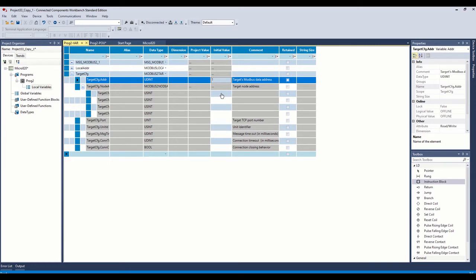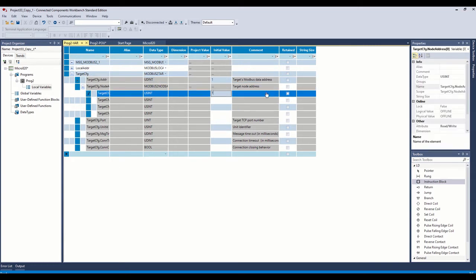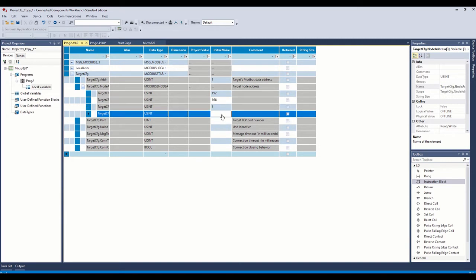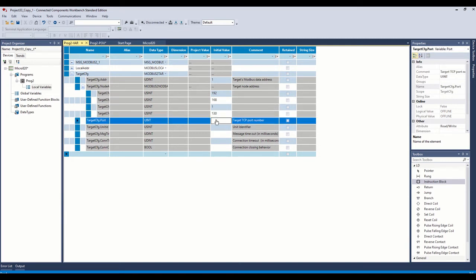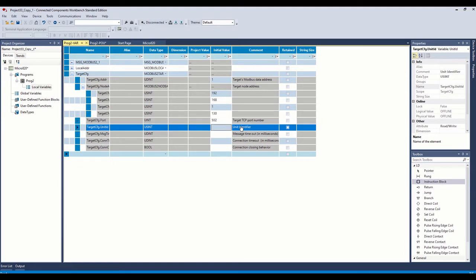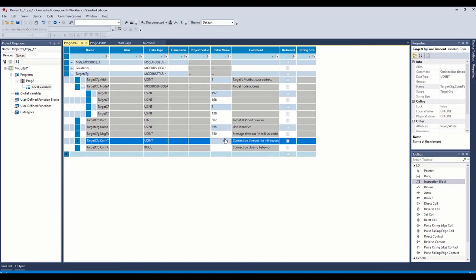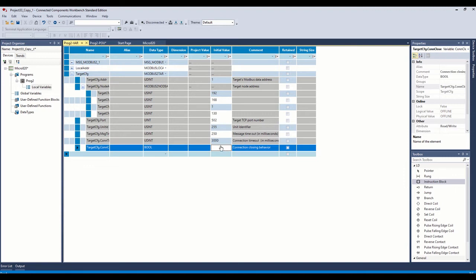The address, that's our IP address in octets here. So we'll go ahead and put that in. Port number defaults to 502, so we'll just leave it there. That's what the port number in the MicroLogix is. The unit identifier, this is used for bridging. So unless you're doing some Modbus bridging, just leave that at 255. And then the message timeout and the connection timeout, we'll just put at those values. The connection closing behavior, we're going to put that at false.